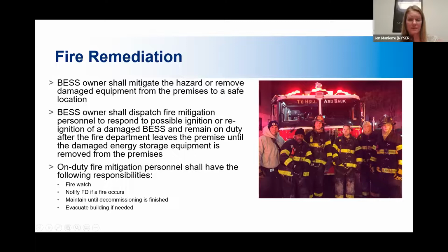In addition to the owner having to dispatch fire mitigation personnel to respond to the scene in a timely manner to help out as well. The other thing that's great about this section of the fire code is the fact that they can relieve the fire department once the fire is out. No one wants the fire department to be out of service and sitting around and babysitting the battery system until it's decommissioned. And the reason that's a concern is because batteries have a lot of energy in them. And even if they had caught fire, maybe not all of the energy was dissipated. So you can snuff out the flames, but then maybe a few hours later, they start to heat up again, and they can reignite hours after the fact, basically.